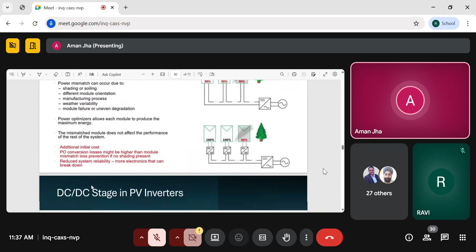Again, the DC-DC stage, as said in earlier slides, is also used for inverter sections. Before the inverter section starts, there is a DC-DC converter. DC-DC boost converters are often integrated for three-phase PV inverters to boost the string voltage up to 600 volts. Higher voltage and lower current is the optimum choice for electrical engineers to reduce losses. Normally we take the panel, which is series-parallel connected since panels are typically configured that way, and as per voltage changing dynamics, we make the boost converter higher than the string voltage of the panel so inverters get a fixed input.